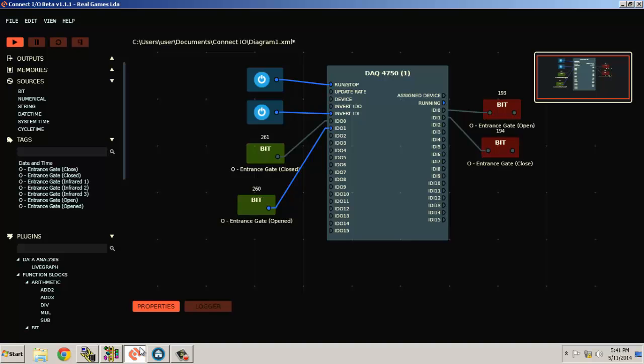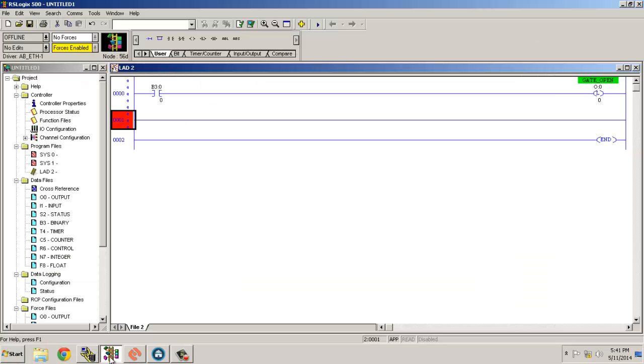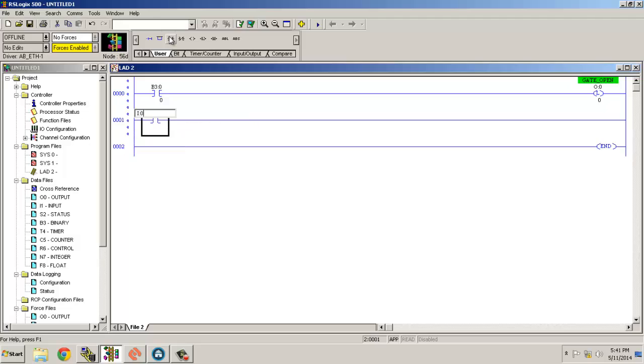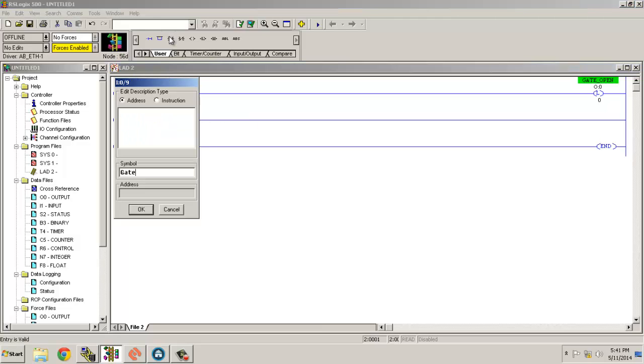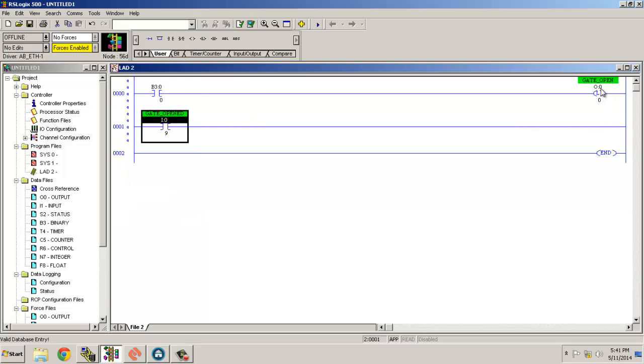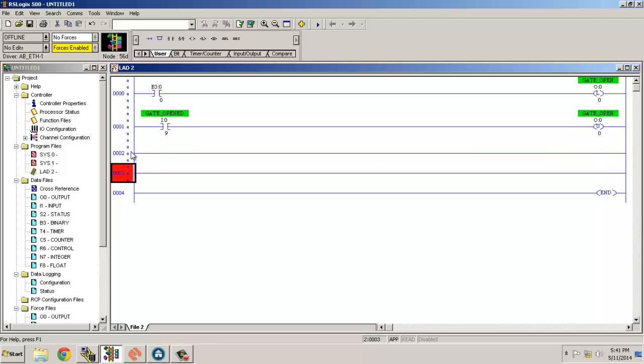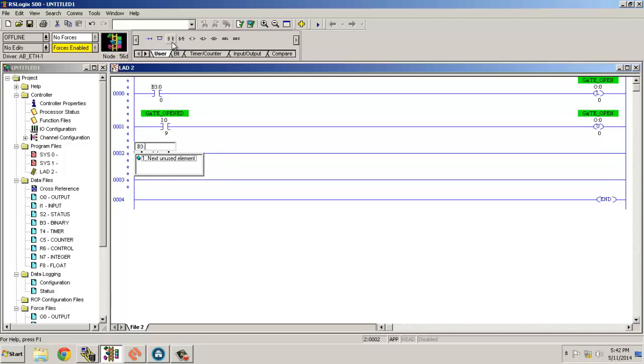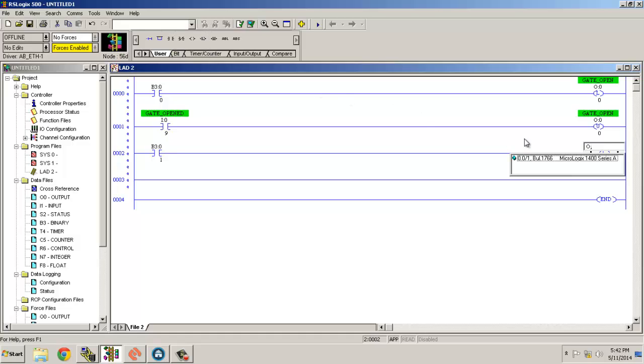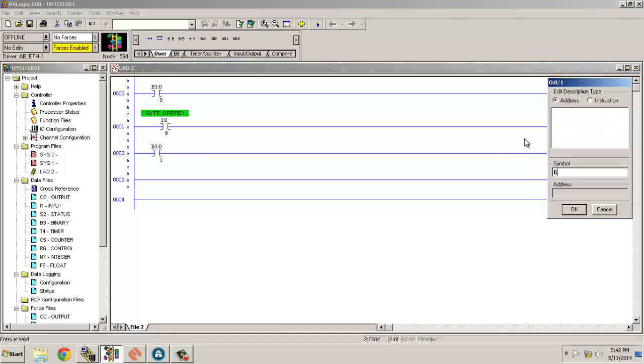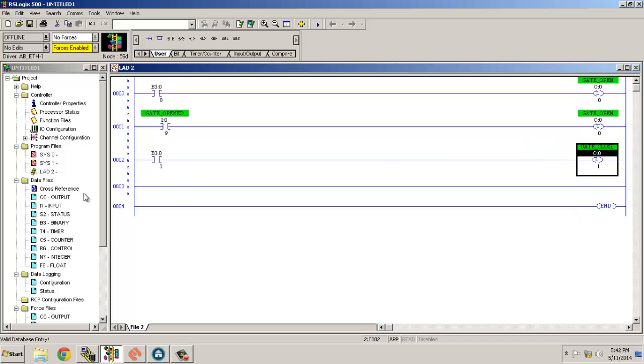I'm just explaining how to interface — you can make as many logic rungs as you like. The feedback for gate opened goes to pin number 9, so it's I:0/9 — this is 'gate opened' and it will unlatch the gate open latch. Now to close the gate, I'll take another bit — B3:0/1. With this I'll latch the close operation, which is O:0/1. The feedback comes at sensor input 8.